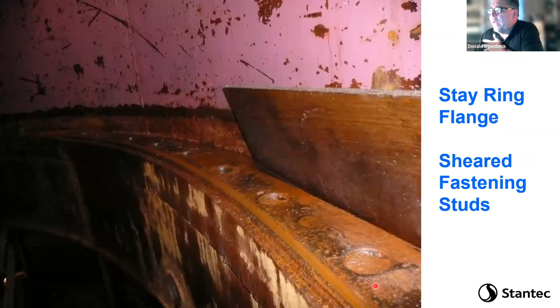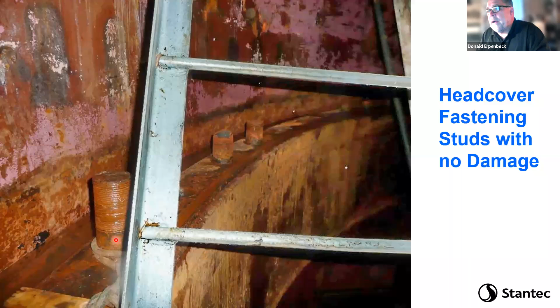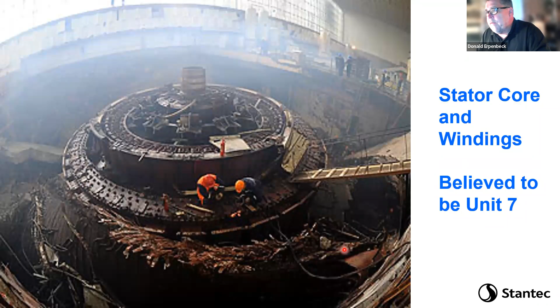Now in the investigation, here is some interesting ones. There were, interestingly enough, 6 studs that didn't fail and weren't even damaged, which shouldn't even be possible. Here's the stator core and windings of this is unit 7. All right, so let's go back to here. So these are those wicket gate pieces in yellow here that you see. And these control the flow in and out of the turbine. And here is the head cover flange. The flange bolts are right here that hold this down.